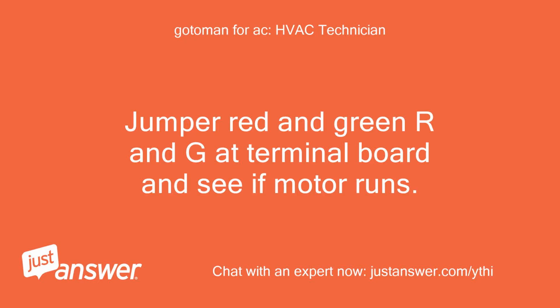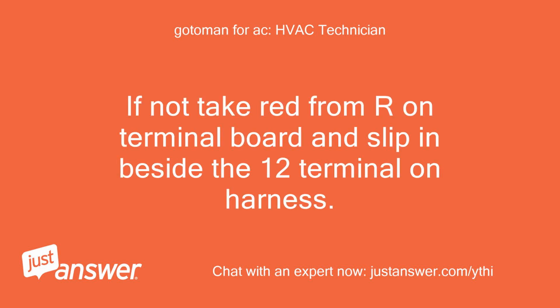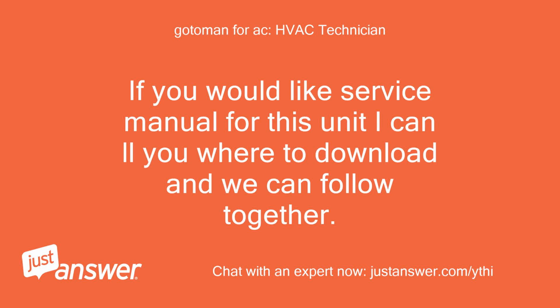Jumper red and green, R and G, at the terminal board and see if the motor runs. If not, take red from R on the terminal board and slip it in beside the 12 terminal on the harness. If you would like the service manual for this unit, I can tell you where to download it and we can follow along together.